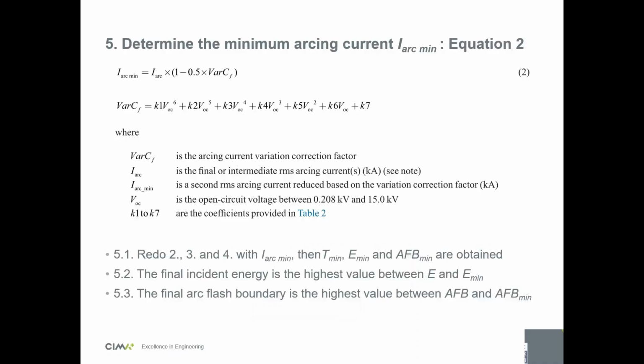Now, you have your energy for the maximum arc current, but now you need to find the minimum arc current. So it's like a second iteration. To find your I arc min, you multiply your I arc by 1 minus 0.5 times var CF. So var CF is the 85% that we talked about earlier. It varies depending on the voltage. And then you get your minimum arc current, then you find the arc time with this one, you find your energy with this one, you find your arc flash boundary with this one, and then your final incident energy is the highest value between the one for I arc and the one for I arc min, and then same for your arc flash boundary.